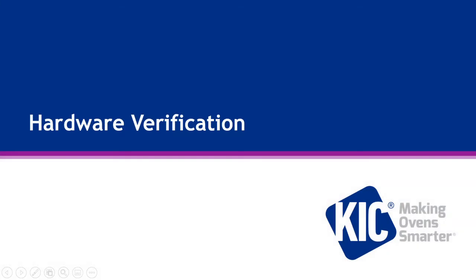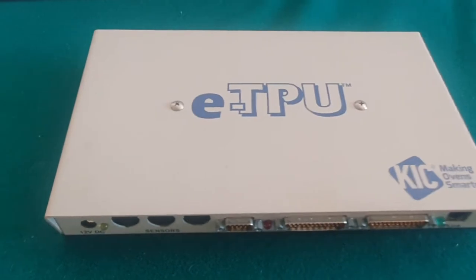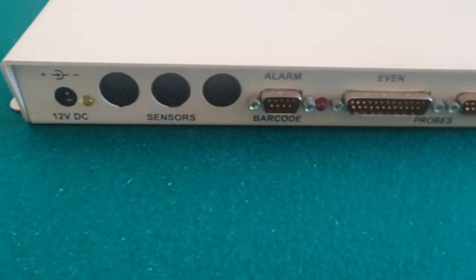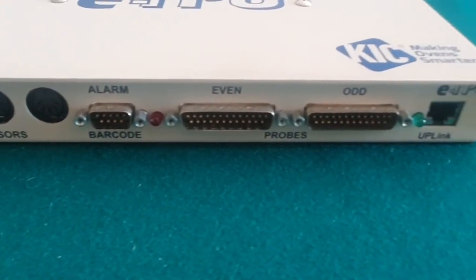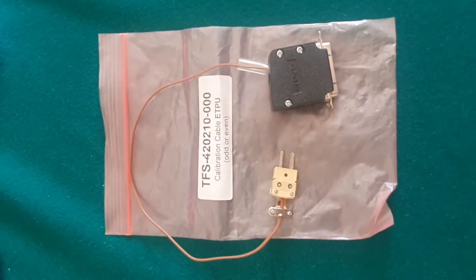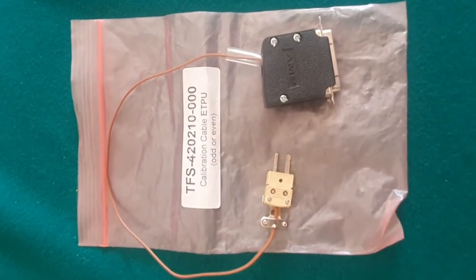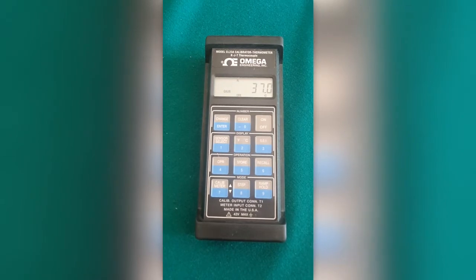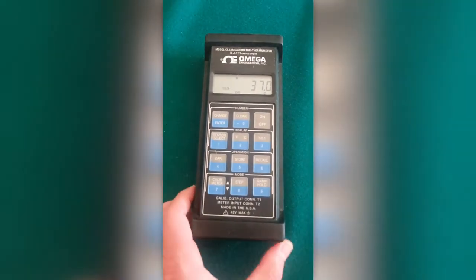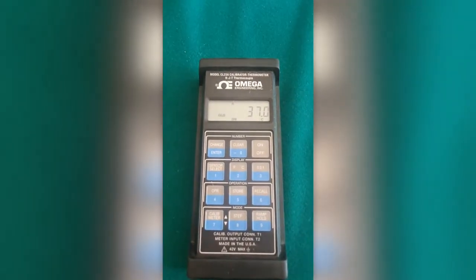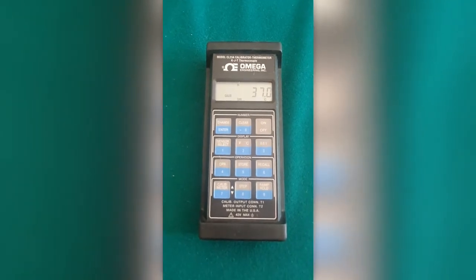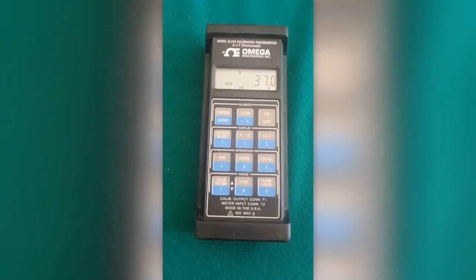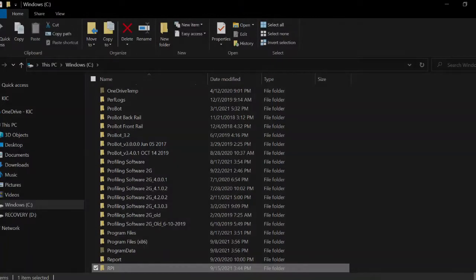Before starting the calibration, please verify that all the correct hardware is available. For the eTPU calibration, you will need an eTPU. The eTPU is the control device that, among other functions, measures temperatures for your KIC automatic system. A calibration adapter. You can get this piece shown in the video from KIC. And the calibrator. In this video, the K-type simulator calibrator, model CL23A from Omega is used. You can purchase your own K-type temperature calibrator.